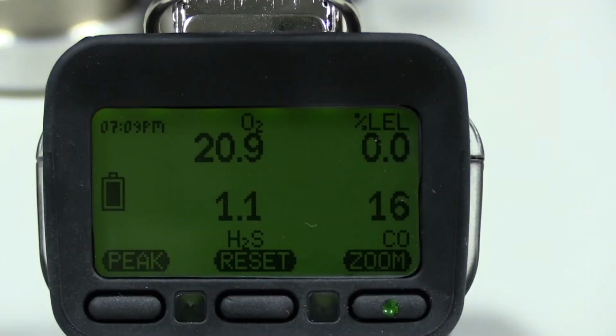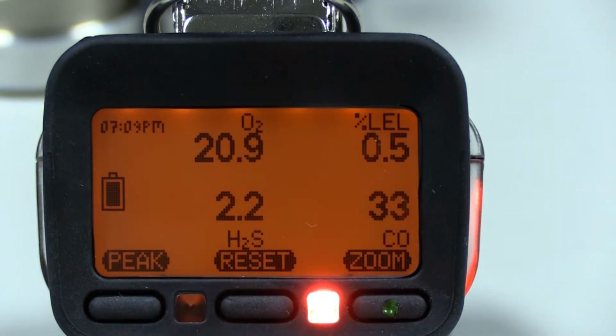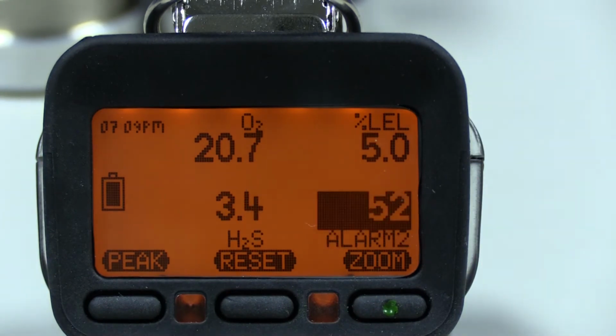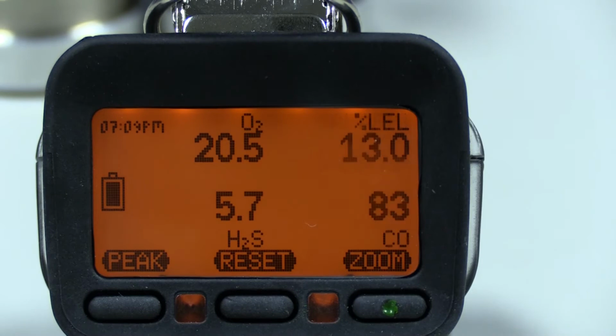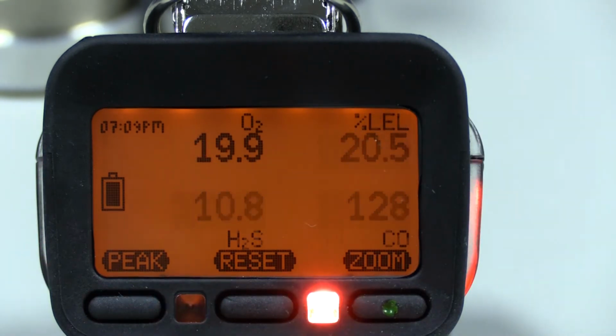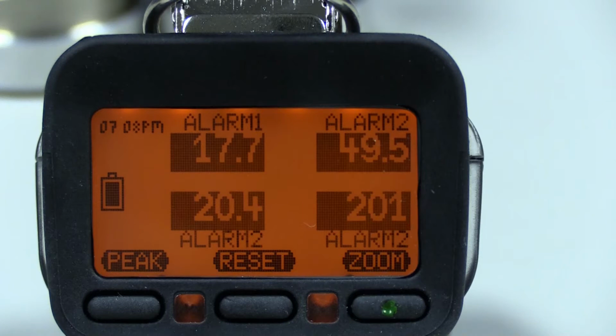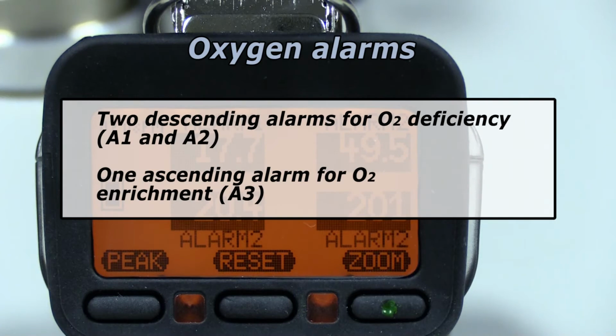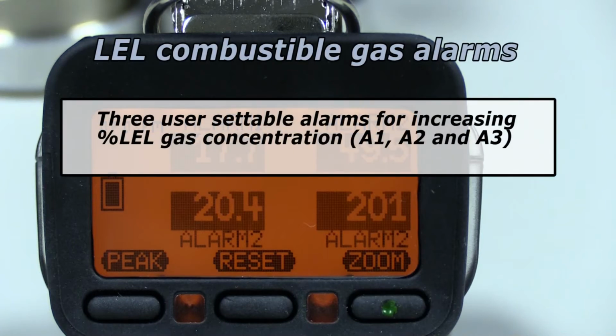The G450 has more than one alarm for each sensor. The display will show the reading as well as the type of alarm. The instrument displays the alarm settings for each sensor during the startup sequence. Oxygen sensors have two descending alarms that are activated by a drop in the O2 concentration. There is also a high alarm that is activated by a rising O2 concentration. Combustible sensors have three user-settable alarms. CO and H2S sensors have 4 alarms for each sensor.